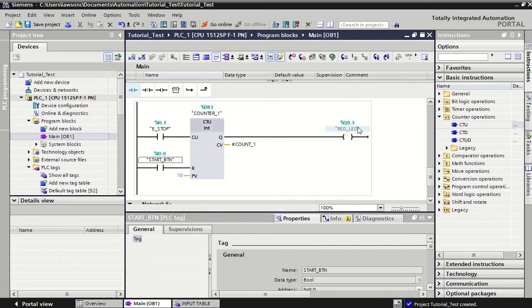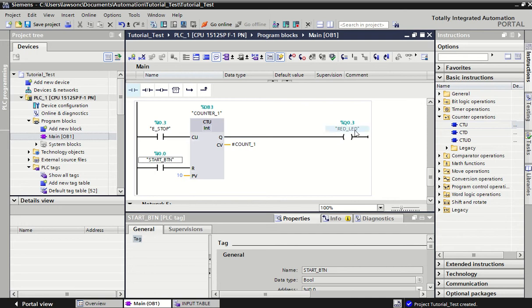When the e-stop gets pulsed to the preset value ten times, this counter becomes fully energized and it will power the red LED. Now that red LED will stay on no matter if the power is lost from the e-stop or if it's continued to be pressed. The red LED stays on. The only way to get the red LED to come off is to hit our reset button, to hit our start button. That will reset our count back to zero and allow us to count up again.